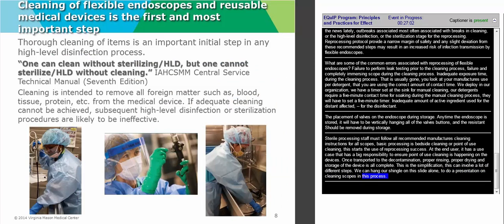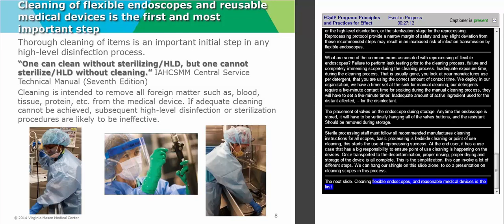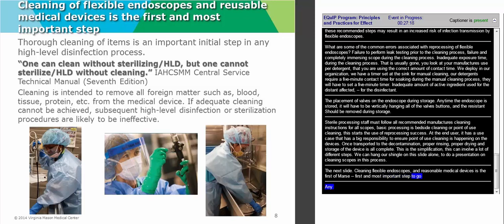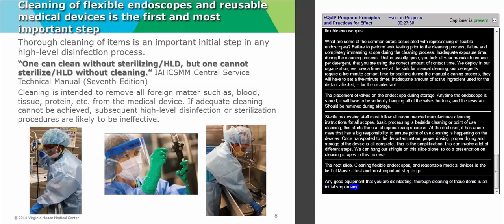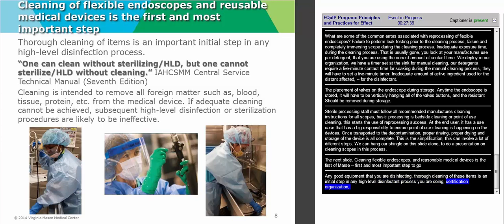So cleaning of flexible endoscopes and also reusable medical devices is the first and most important step. Whether it be TEE probes, PMB probes, CMAC blades, anesthesia equipment, whatever item it is that you are high-level disinfecting, thorough cleaning of these items is an important initial step in any of the high-level disinfection processes that you are doing. A quote from our certification organization, IAHCSMM, out of their textbook is, "One can clean without sterilizing or high-level disinfecting, but one cannot sterilize or high-level disinfect without cleaning." Cleaning is the most important part, or the first steps in all this processing.